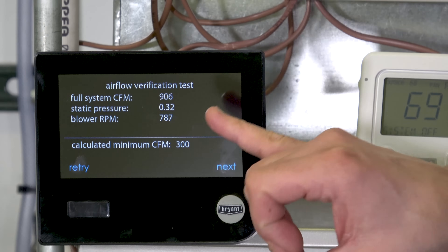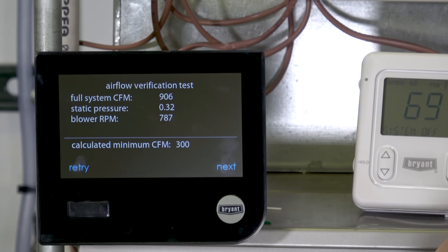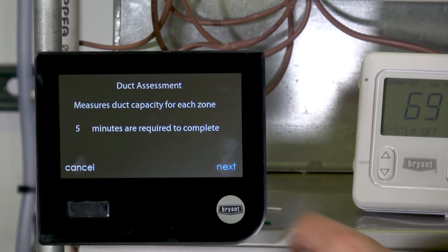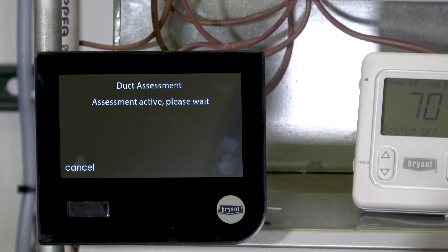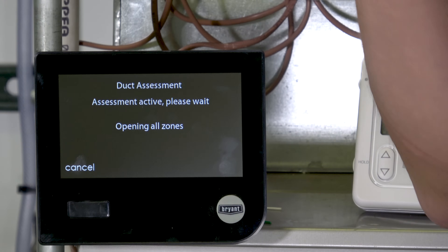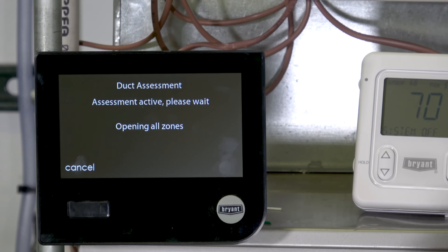The calculated minimum CFM is 300, and with a zoning system that's important: between our three zones, if I want to run heating or cooling for just one zone, that zone needs to take 300 CFM. With three zones it takes five extra minutes to do an individual test for each zone — two zones would take three minutes, eight zones would take ten. It opens zone one alone, closes two and three, tests CFM and static, then cycles through each. We'll speed that up on camera.